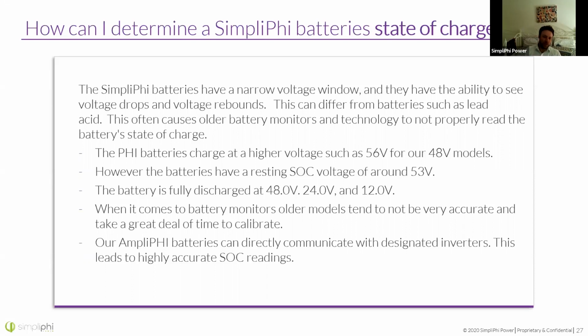Some quick notes here: these batteries charge at a higher voltage, such as around 56 volts for our 48 volt models. However, they have a resting state of charge, which I define as load being on the system and the batteries no longer in a state of charge. At about 53 volts, they're 100% charged. The battery is fully discharged at 48 volts in a 48 volt situation, 24.0 in a 24 volt situation, and 12.0 in a 12 volt situation.